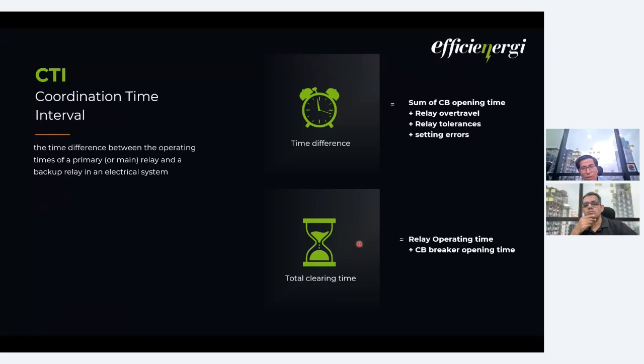So to have knowledge of these three is much more important. Some of the people might be thinking that just adding up the breaker opening time would solve the CTI issues, but the answer is no. We also have to see the relay over travel and relay tolerances.